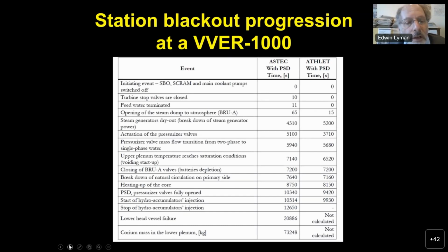And the lower head of the vessel, that is that melt through I was talking about, would happen in less than 10 hours. So in that situation, there's a pretty short window for people to intervene to try to get cooling restored before the core starts to melt. Once you start having melting, then it becomes much harder to arrest that before you lead to this situation of vessel breach.